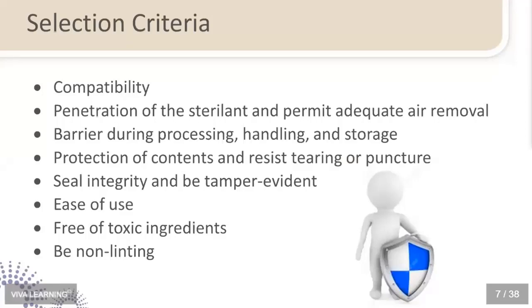You also have to make sure that the material is compatible with the type of sterilization method that you're using. And this is really important if you're using something like the plastic pouches that often come on a roll. Many of those are not always cleared for steam sterilization. So you want to make sure that you're reading the detailed information if you are in fact buying a new product, that it is going to be compatible with your method. It has to be suitable for the type of items that are being sterilized. As I said before, you need to make sure that you have your manufacturer's instructions for use available. We have to make sure that it's going to allow penetration of the sterilant.